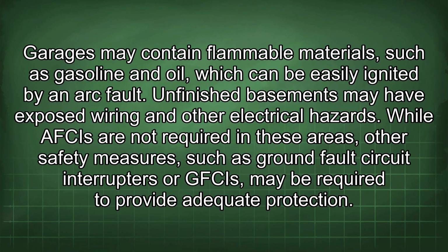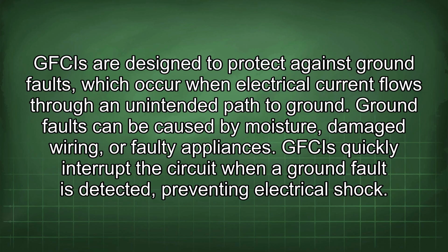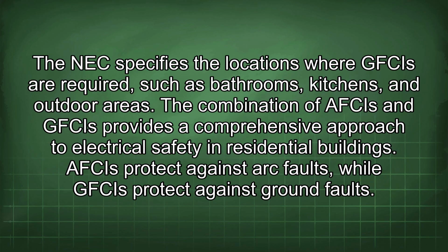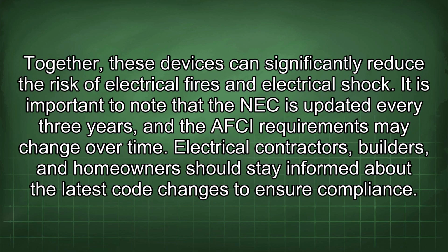While AFCIs are not required in these areas, other safety measures, such as ground fault circuit interrupters or GFCIs, may be required to provide adequate protection. GFCIs are designed to protect against ground faults, which occur when an electrical current flows through an unintended path to ground. Ground faults can be caused by moisture, damaged wiring, or faulty appliances. GFCIs quickly interrupt the circuit when a ground fault is detected, preventing electrical shock. The NEC specifies the locations where GFCIs are required, such as bathrooms, kitchens, and outdoor areas. The combination of AFCIs and GFCIs provides a comprehensive approach to electrical safety in residential buildings. AFCIs protect against arc faults, while GFCIs protect against ground faults. Together, these devices can significantly reduce the risk of electrical fires and electrical shock.